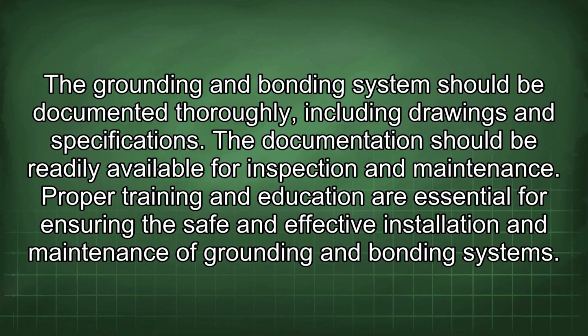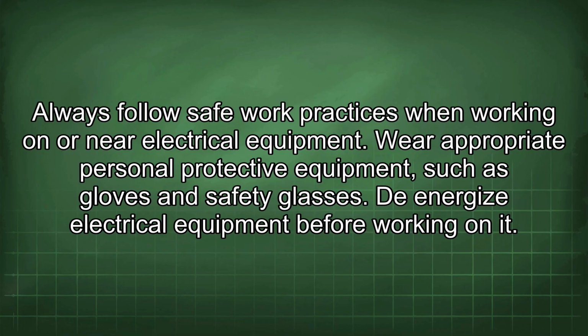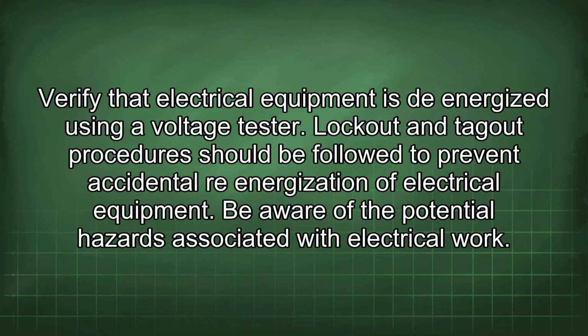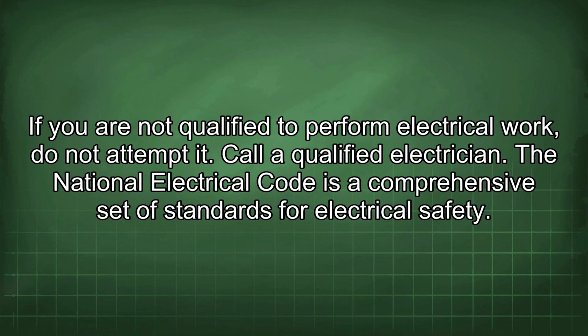Proper training and education are essential for ensuring the safe and effective installation and maintenance of grounding and bonding systems. Always follow safe work practices when working on or near electrical equipment. Wear appropriate personal protective equipment, such as gloves and safety glasses. De-energize electrical equipment before working on it. Verify that electrical equipment is de-energized using a voltage tester. Lockout and tagout procedures should be followed to prevent accidental re-energization of electrical equipment. Be aware of the potential hazards associated with electrical work. If you are not qualified to perform electrical work, do not attempt it.